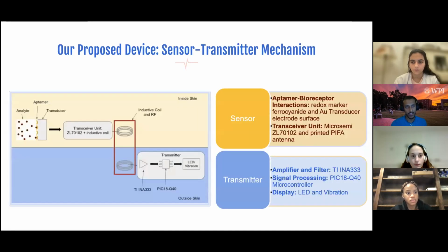Next up is the sensor transmitter mechanism. Troponin-based aptamer utilizes the redox marker ferrocyanide and gold transducer surface to form a potential gradient that can be quantitatively measured as a change in voltage. This decreases the voltammetric signal produced by the aptamer, which can be measured quantitatively. Once the electrical signal is generated from the aptamer, the signal will go through a built-in transceiver unit to transmit the signal using a specific radio frequency to the transmitter, which is placed over the skin.